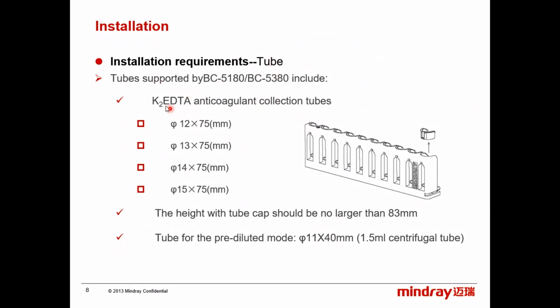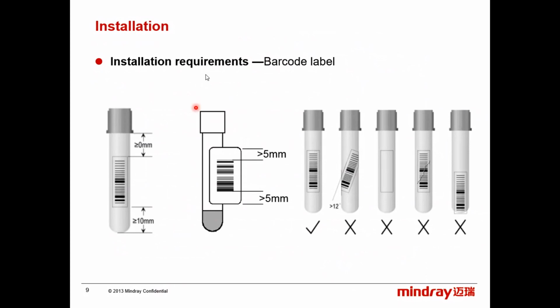Okay, for the tubes, these are the tubes required or supported. Anticoagulant collection tubes, K2EDTA. All of these tubes are supported. Tube for pre-diluted mode, 1.5 ml centrifugal tube. For the barcode label, pay attention to or train the operator to stick the labels well, because this model doesn't support the rotational barcode scanning. In some other models, let's say the BC-6000 or the BC-700 series with autoloader, they support the barcode rotation. So here make sure to correctly install the label like that, not like this, not like that.